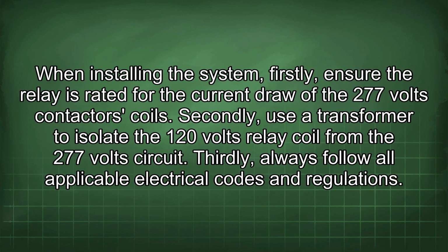When installing this system, firstly, ensure the relay is rated for the current draw of the 277 volts contactors coils. Secondly, use a transformer to isolate the 120 volts relay coil from the 277 volt circuit. Thirdly, always follow all applicable electrical codes and regulations.